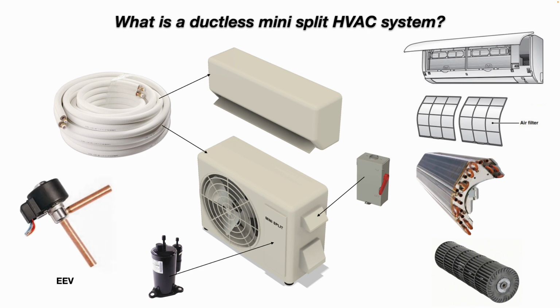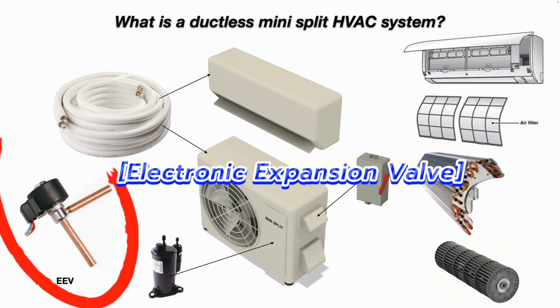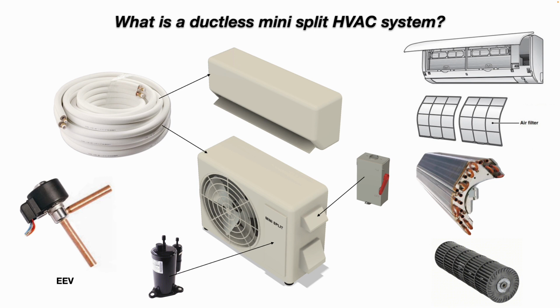And oftentimes these ductless mini split systems will use an EEV instead of a TXV. EEVs are more efficient or precise in controlling the refrigerant flow through the system.